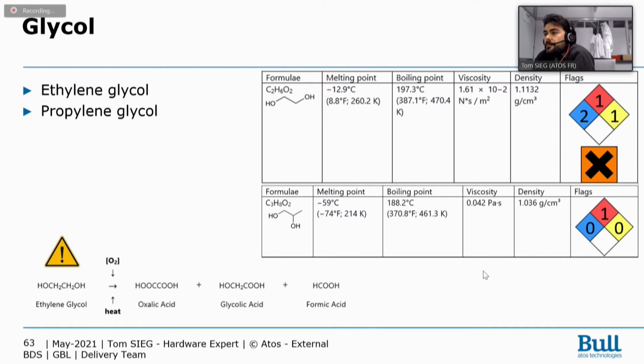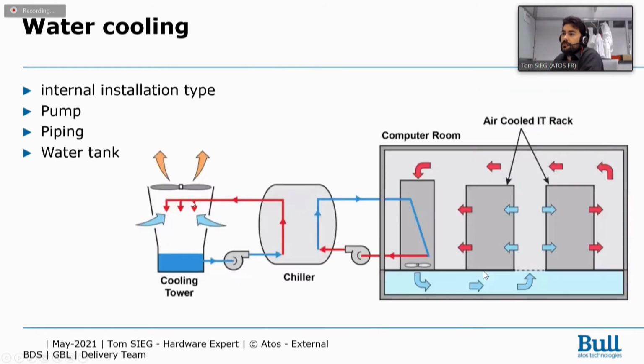Each has specifications, melting point, etc., depending on where you install your data center, what your need is, if it's closed, if it's open, etc. In the case of a water tower, you will not be able to use glycol in this circuit.